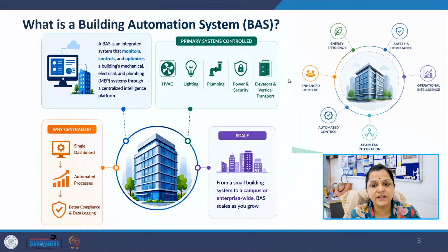This centralization also enables automated interlock between systems. For example, during a fire event, the fire alarm systems can trigger HVAC shutdown automatically to prevent smoke spread in different areas of the building. Another important function is data logging. Building automation system or BAS continuously records operational information for compliance, diagnostic, and performance analysis. The scale of building automation system varies significantly. Small retail units may operate with only 50 control points, while airports or large campuses may contain hundreds of thousands of connected points. Building automation system, therefore, functions as the operational backbone of modern intelligent buildings.